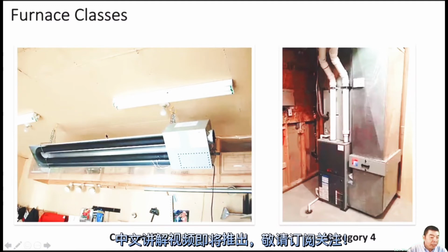These are infrared units with sealed combustion, so all the combustion air should be sealed. You will generally find this unit in garages or shops. I haven't found any like this in the living area. Be mindful of any corrosion or heavy debris on the tubes. For this one, it's easy. You can easily find the corrosion because it's airtight and even some are watertight, and that corrosion is normal to find.